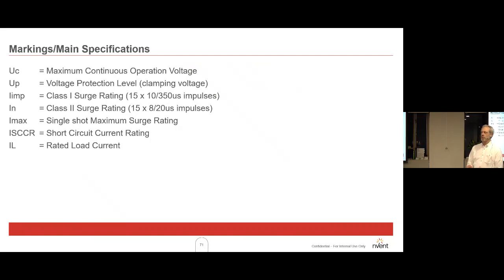There are a number of parameters to specify for a surge diverter, including the maximum continuous operating voltage, which is the maximum voltage that it will keep working at without burning out or being consumed. The UP is the voltage protection level, which is what it lets through to the load when there's a surge. That's based around a specific size test current, test surge, and all surge protection manufacturers should use that same test waveform so that you can compare apples with apples, ideally.